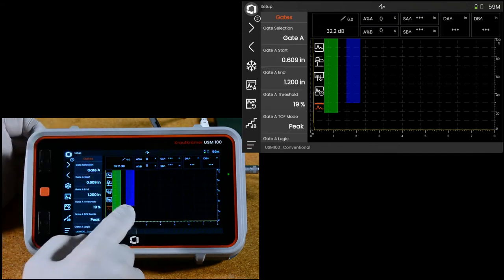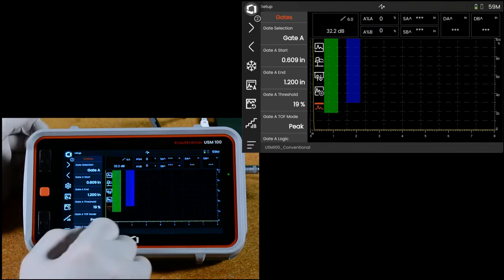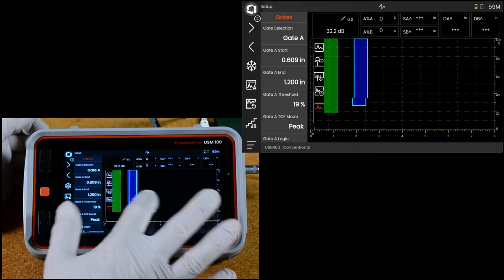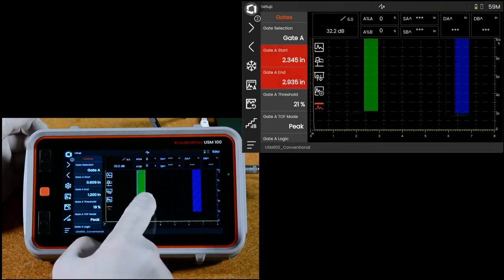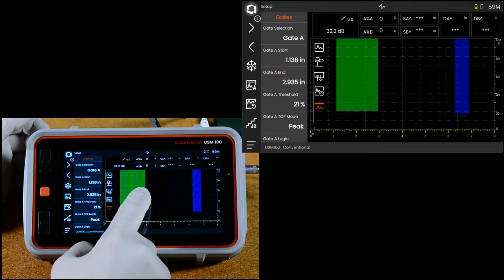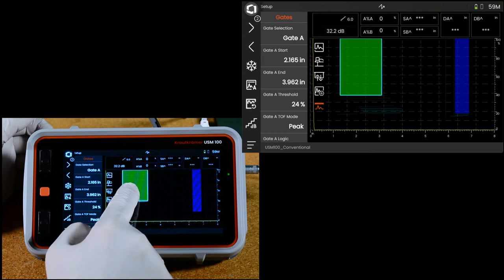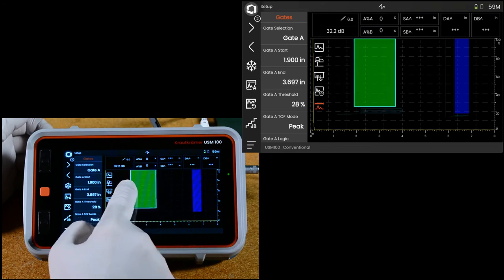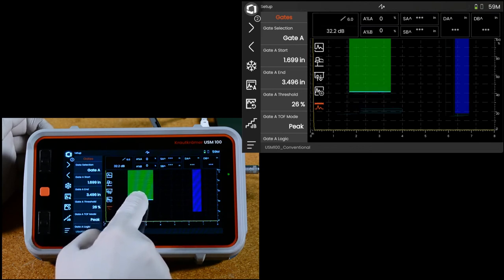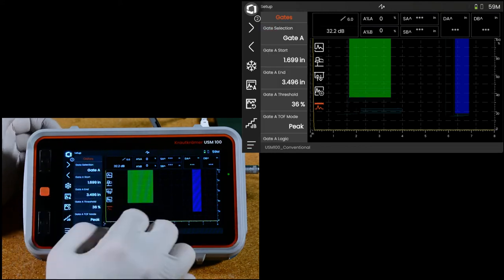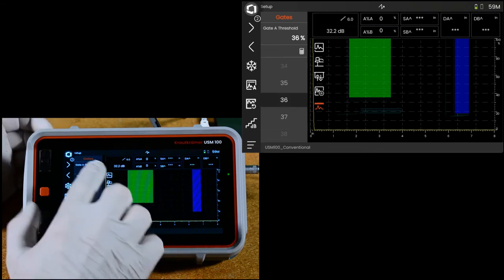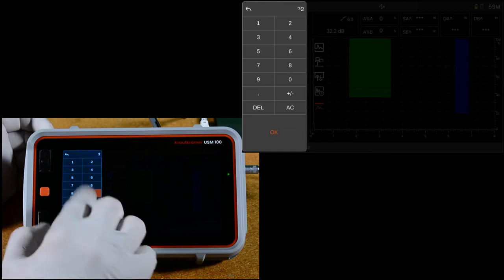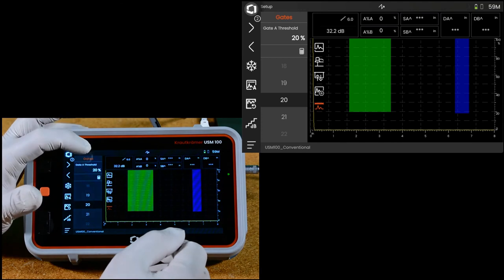Now, one thing in the USM 100 because of the touch screen, it's a lot handier normally to adjust the gate simply by clicking or touching on the gate and dragging it around on the screen. You can set delay, width, and threshold all by simply grabbing one edge or the other edge of the gate itself or grabbing just the threshold. And you see when you let up, the matching parameter moves as well. Or I can come in here, if I just knew I wanted to set that straight to 20%, I can set it to 20% and everything synchronizes that way.